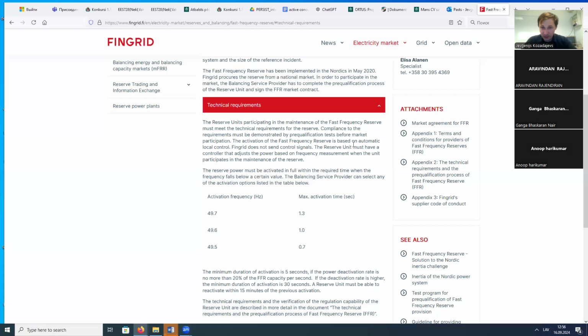The activation of the fast frequency reserve is based on automatic local control. Fingrid does not send control signals. The reserve unit must have a control that adjusts the power based on frequency measurements when the unit participates in the maintenance of reserve. And for this, there is a very interesting example. Some years ago in Finland, Siemens built a hypermall, a shopping mall. For their purposes, there is battery storage for all the automation systems in a mall, for ventilation, air conditioning, heating, lighting, and so on. So they have a really big battery storage. And this mall is a pilot project, designed by Siemens, participating in this fast frequency reserve.